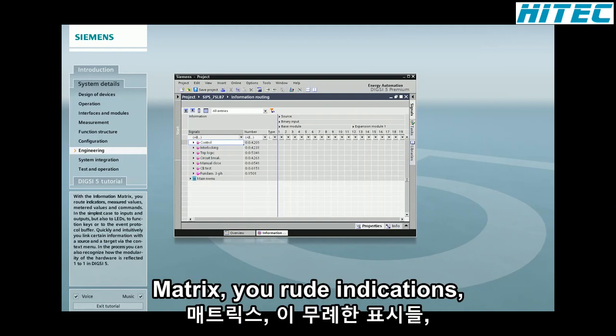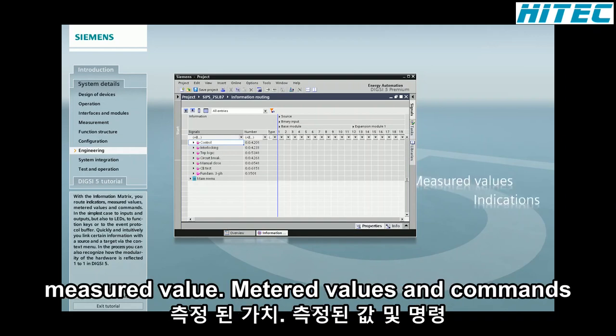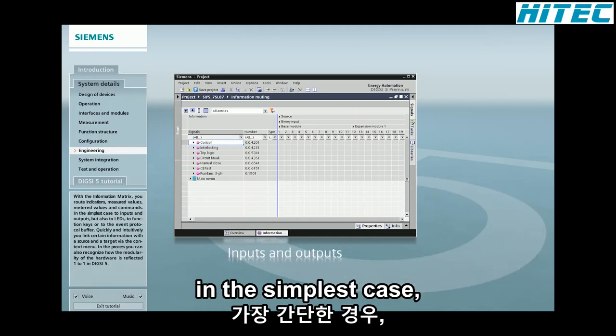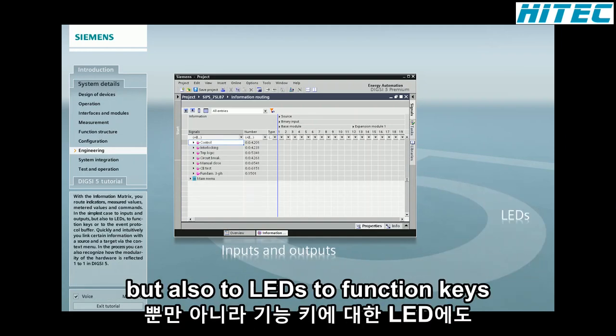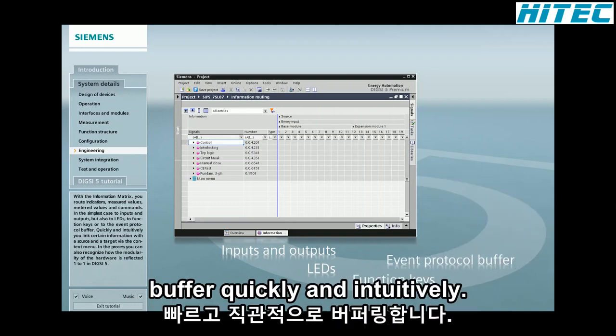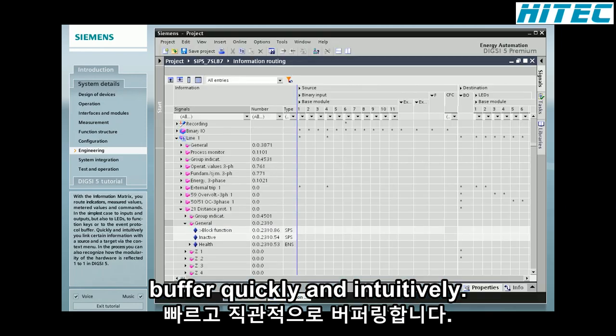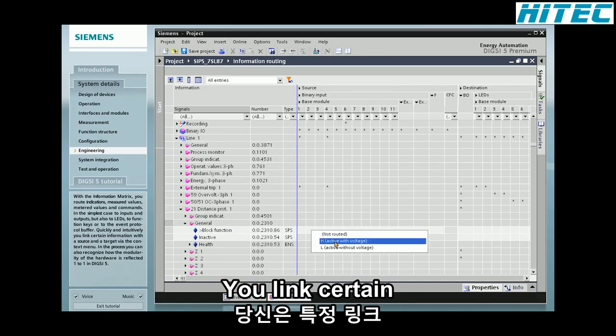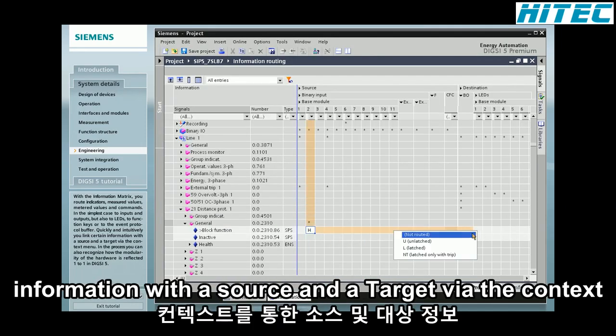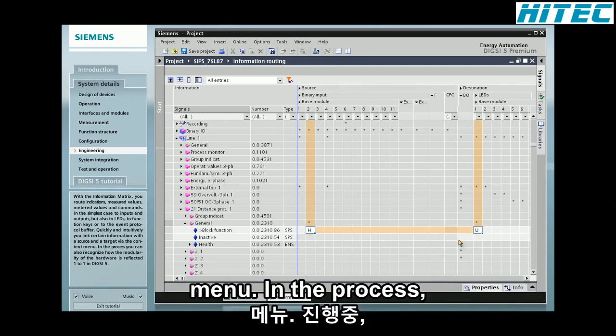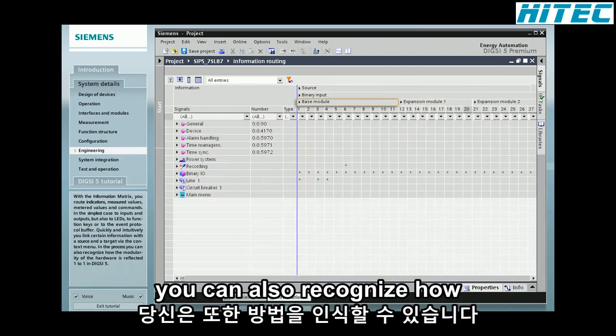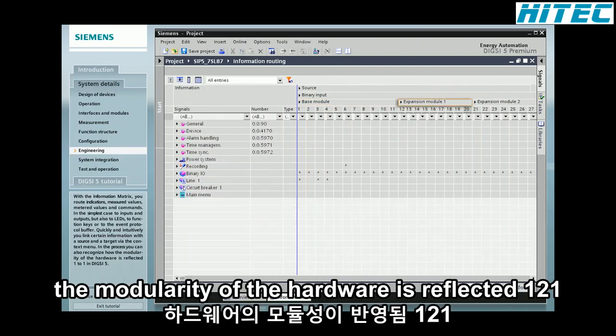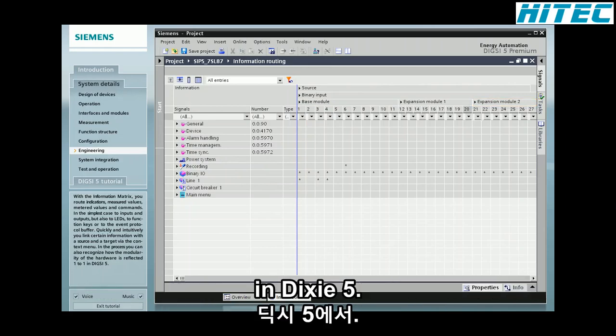With the information matrix, you route indications, measured values, metered values, and commands. In the simplest case, to inputs and outputs, but also to LEDs, to function keys, or to the event protocol buffer. Quickly and intuitively, you link certain information with a source and a target via the context menu. In the process, you can also recognize how the modularity of the hardware is reflected one-to-one in DIGSI-5.